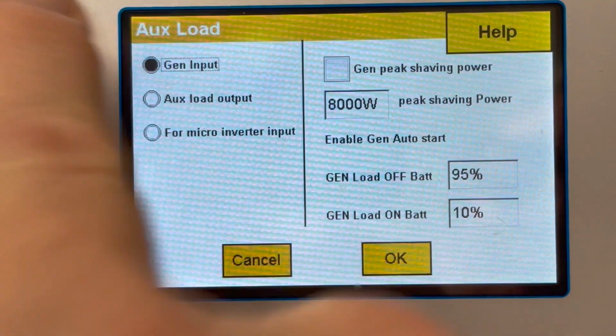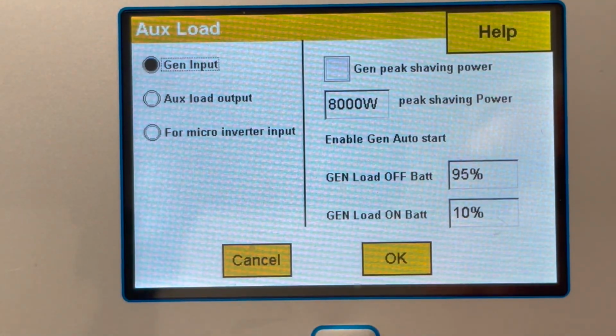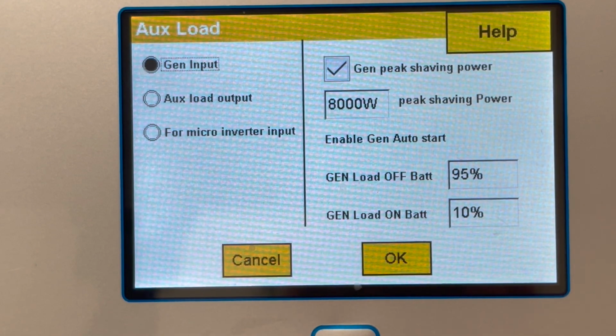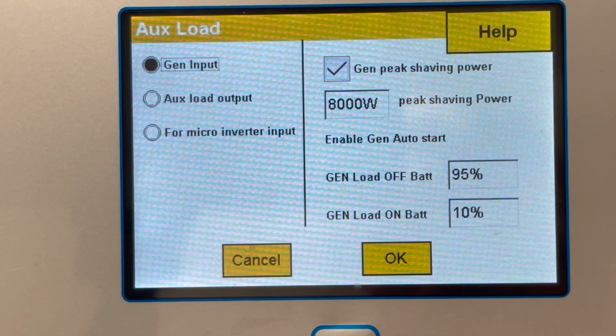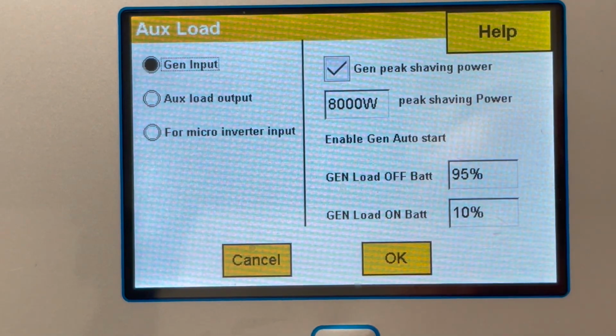You've also got another thing here, which is peak power shaving. Peak power shaving is where you use the CT coil to measure the power. For example, if your supply is limited to, say, 8 kilowatt, or 10, and you want more power, or if you've got a 5 kilowatt generator and you need to run 10 kilowatt, you might put in another 5 kilowatt inverter. So this power is additional power. This will output when the power reaches the limit on here. So this is the limit.